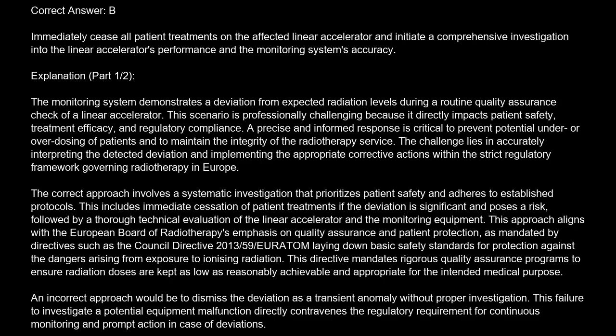Explanation: the monitoring system demonstrates a deviation from expected radiation levels during a routine quality assurance check of a linear accelerator. This scenario is professionally challenging because it directly impacts patient safety, treatment efficacy, and regulatory compliance. A precise and informed response is critical to prevent potential under- or overdosing of patients and to maintain the integrity of the radiotherapy service. The challenge lies in accurately interpreting the detected deviation and implementing the appropriate corrective actions within the strict regulatory framework governing radiotherapy in Europe.